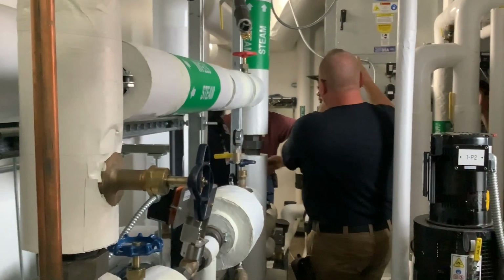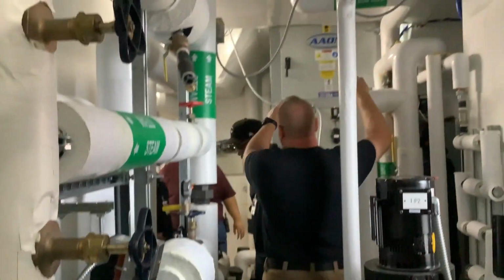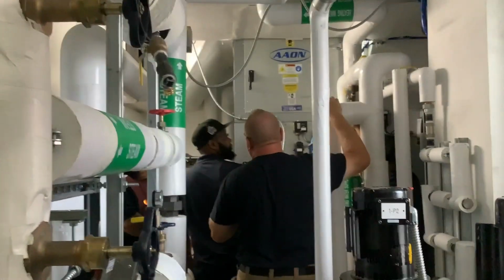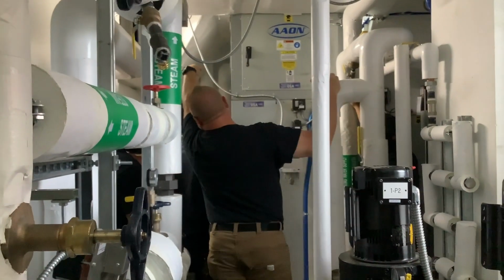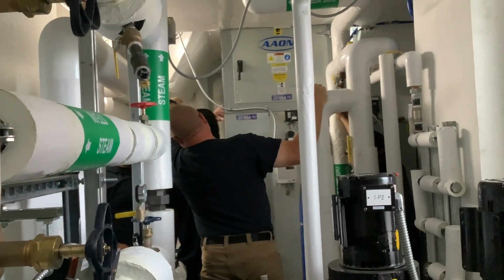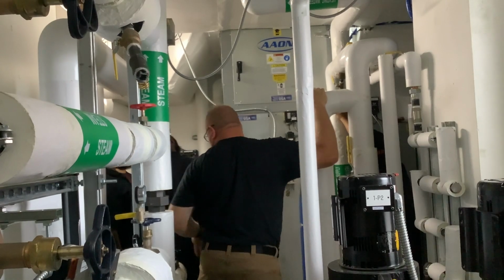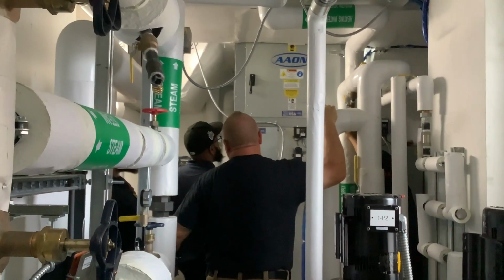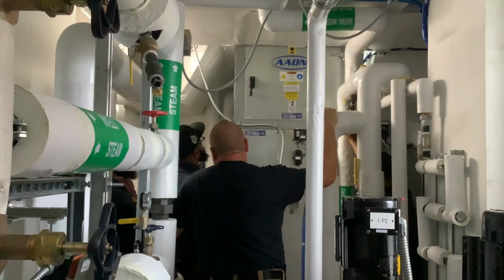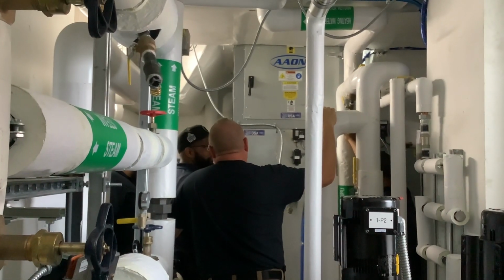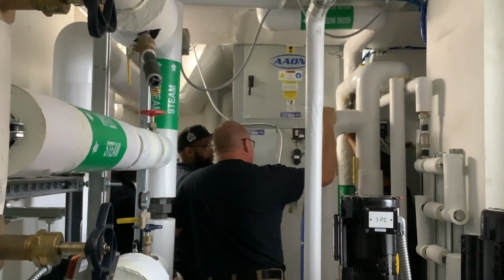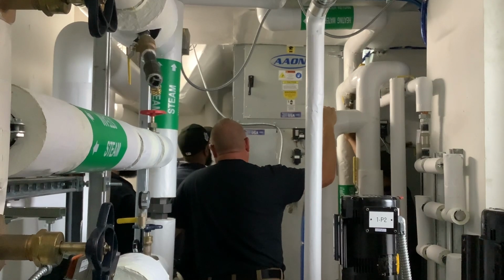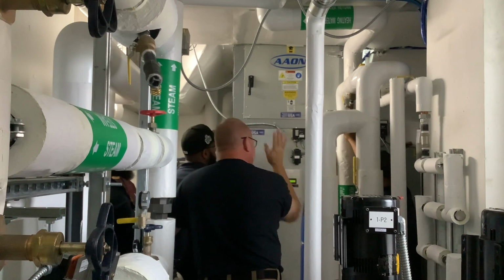We're going to turn around right behind you now and look at this. Before we go too far, you see those bolts right there? That panel there, that's where your blower's at. That is a direct drive blower with a reverse curve wheel on it. You guys know what a reverse curve is, right? I'm sure you deal with them all the time with exhaust fans and stuff. A lot of times I'll get a call and they'll say the wheel's running backwards, because it's supposed to be throwing it a certain way.